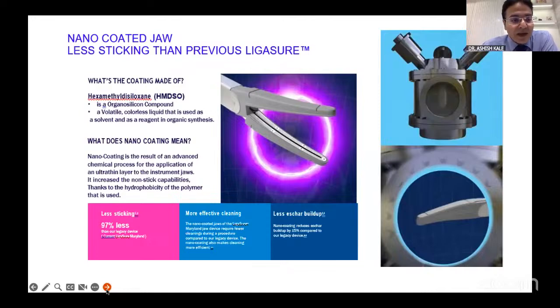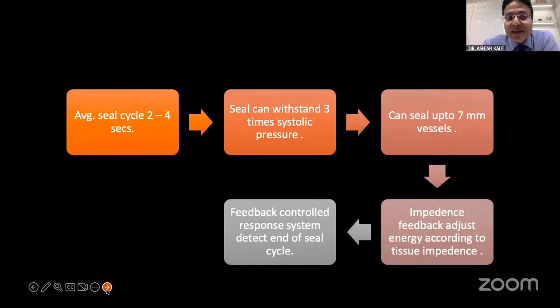When coagulation is completed, the average sealing cycle is 2 to 4 seconds. The seal can withstand 3 times the systolic pressure, and it can seal vessels up to 7 millimeters. There is an impedance of the tissue. Once the coagulum is formed, the tissue impedance signals the device, and it gives a response that the coagulation has been formed, and then the cutting cycle continues.